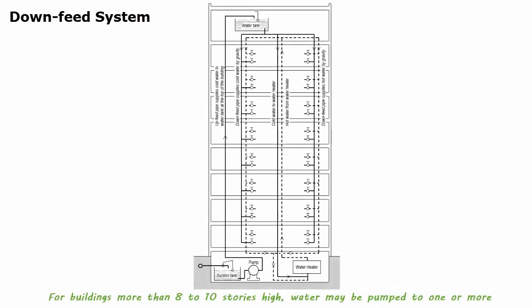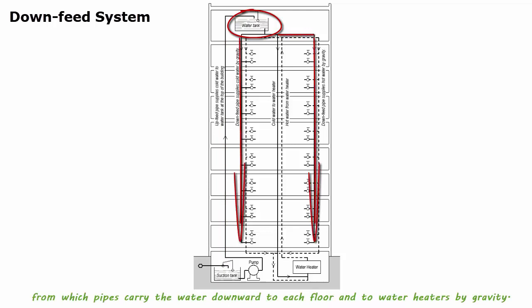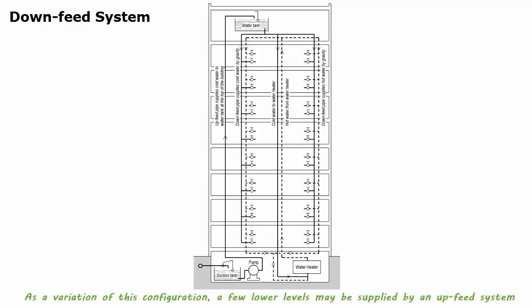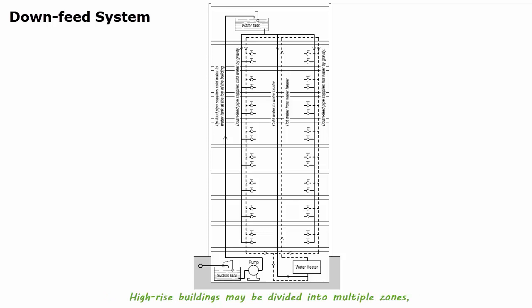For buildings more than 8 to 10 stories high, water may be pumped to one or more elevated storage tanks at the top of the building, from which pipes carry the water downward to each floor and to water heaters by gravity. As a variation, a few lower levels may be supplied by an upfeed system under pressure from a public main, while the remaining upper floors are served by a downfeed system. High-rise buildings may be divided into multiple zones, each served by a separate downfeed system.